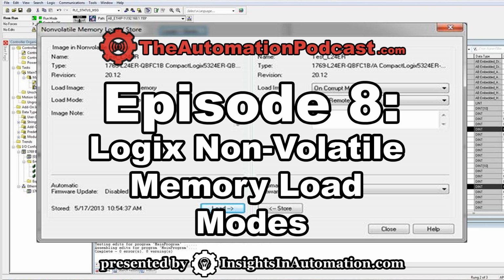Now at this point, Program 1 is in non-volatile, and Program 1 is still in the memory of the processor. So let's open up Program 2, download it to the processor, and then cycle power to the processor to ensure that Program 2 remains in the processor's memory. In other words, we put Program 1 on the non-volatile storage and set it to only load on user initiated when we do it ourselves.